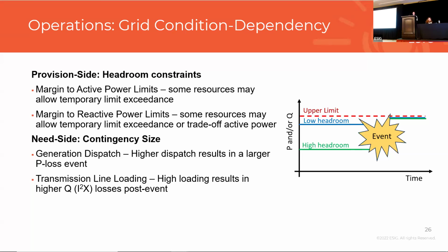If we take the active power limits for example, I'll draw a contrast between a synchronous machine-based technology and an inverter-based technology. For a synchronous machine on active power, if you're at the active power limit - say you're in temperature control on a gas turbine - you're maxed out and can't go any higher.